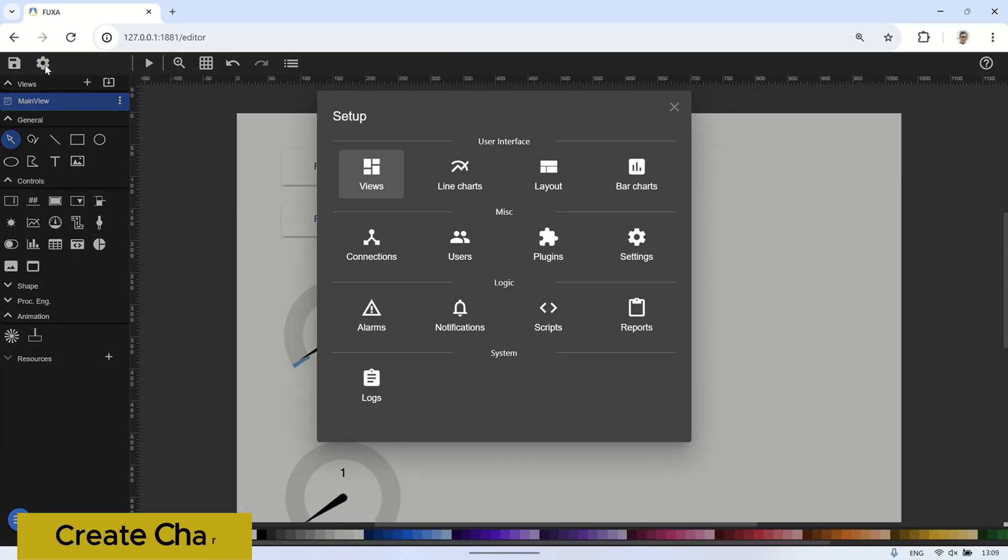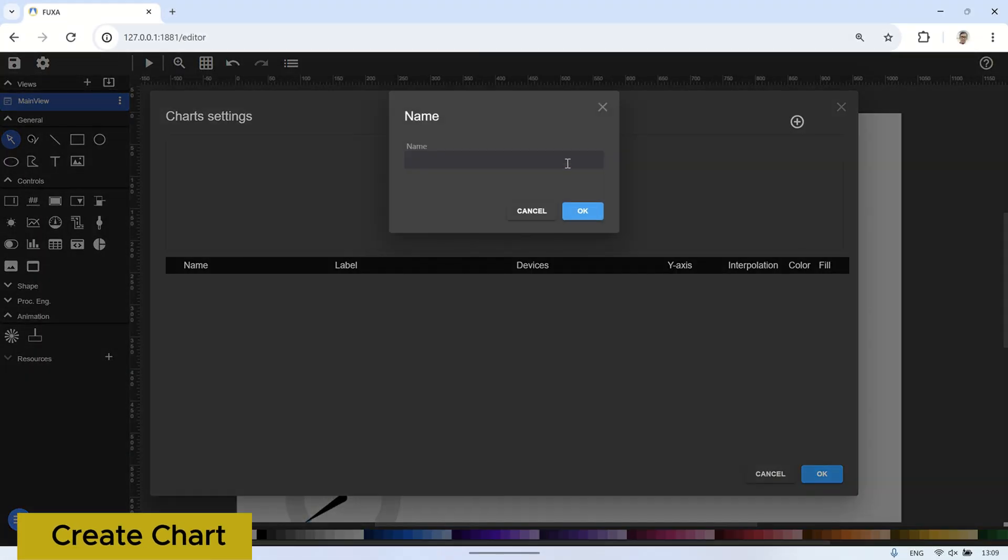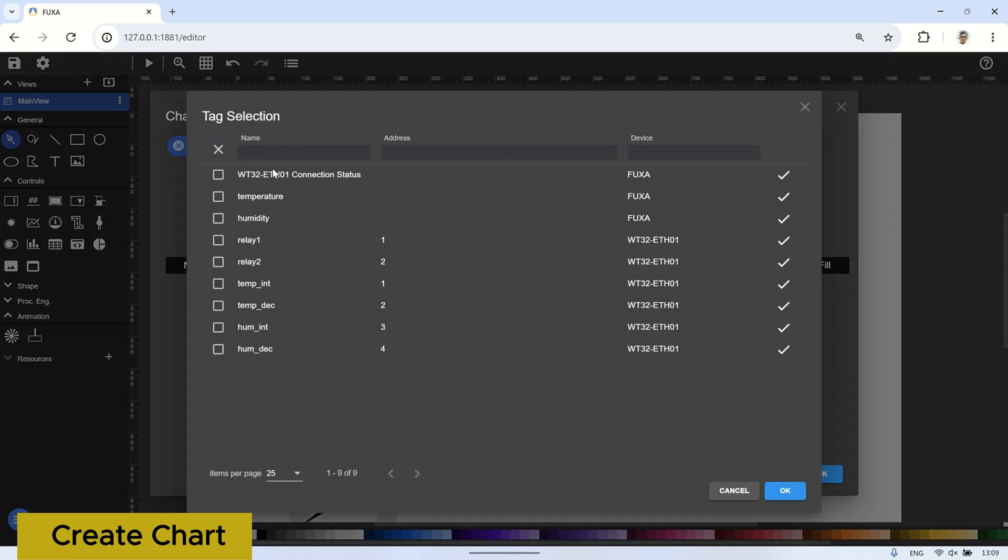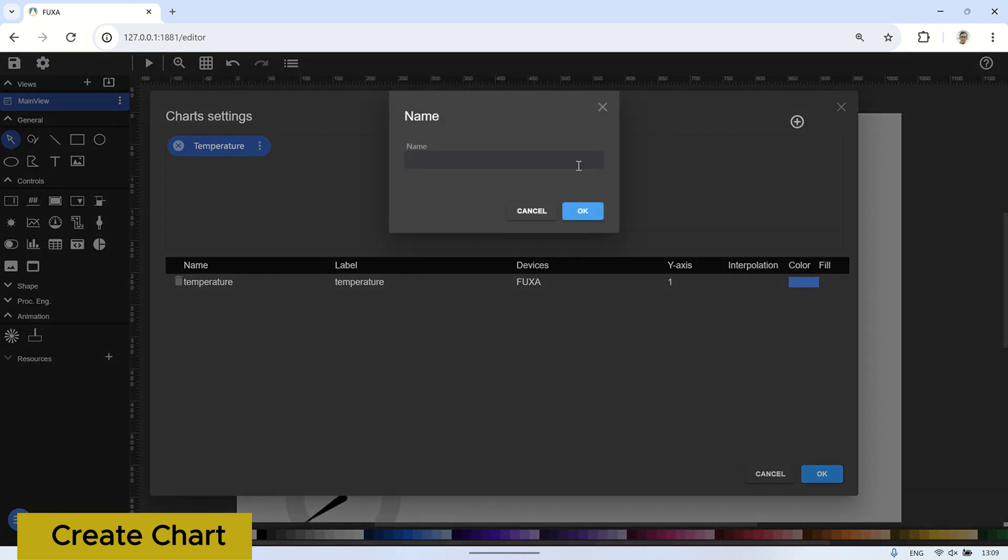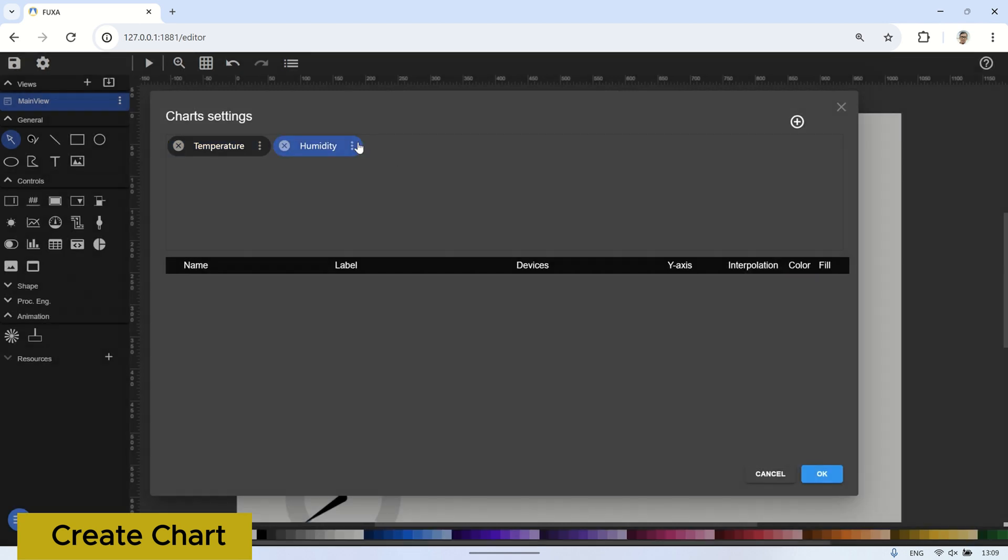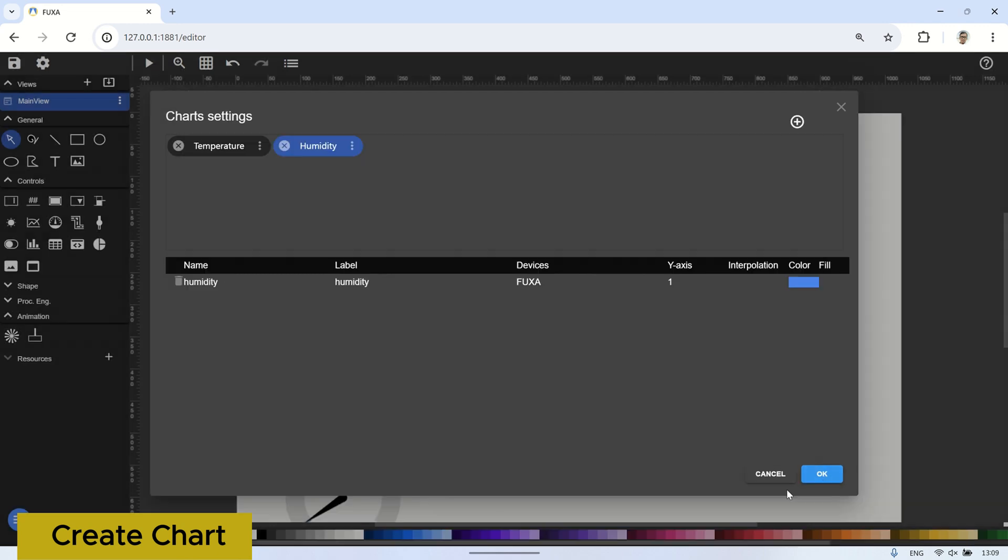To create a chart, go to the setup menu and select line chart to open the chart settings. Click the plus button to add a chart, name it temperature, then click add line and select the temperature tag. Repeat the same steps to create a humidity chart. Now in the chart settings, we have two charts, temperature and humidity, ready to be displayed in the visual chart on the SCADA.